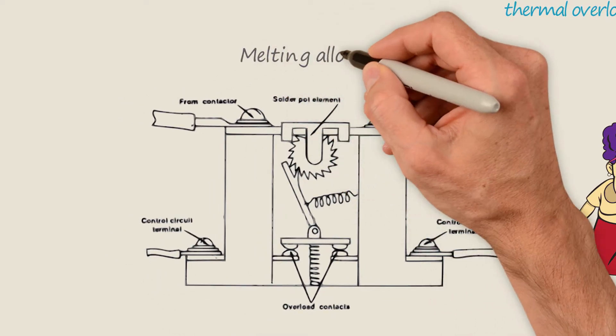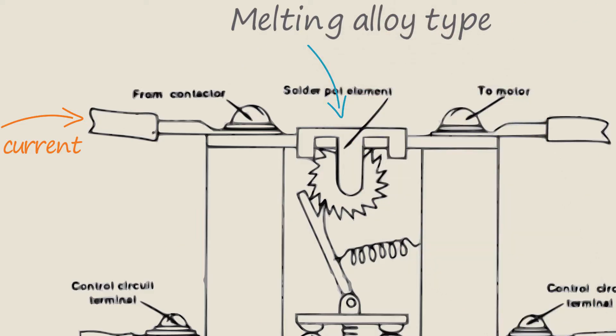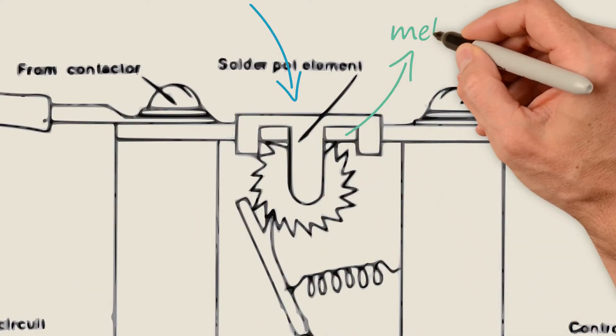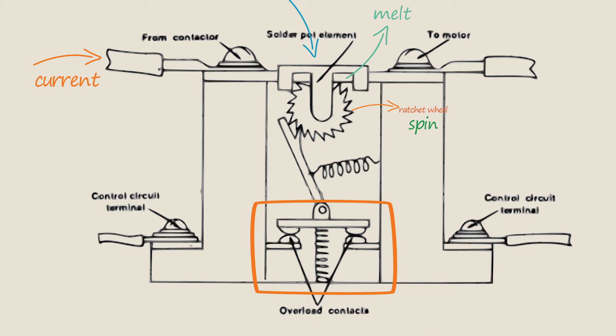In melting alloy type, the motor current passes through a small heater winding. The heat causes a special solder to melt, allowing a ratchet wheel to spin, and this opens the control circuit contacts.